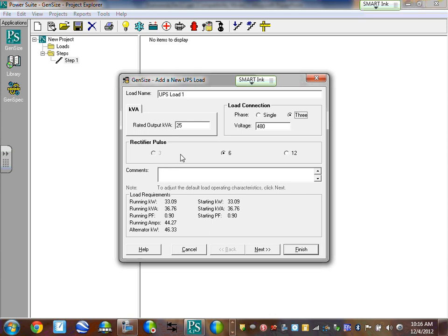A rectifier pulse on the UPS is kind of how the power supply operates. A 6-pulse rectifier is a default. 12 would be much better. We're not sure who's going to be supplying the UPS, so we'll go with a 6-pulse.